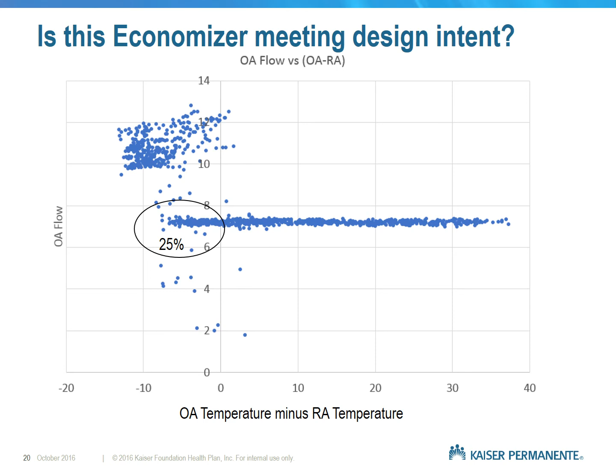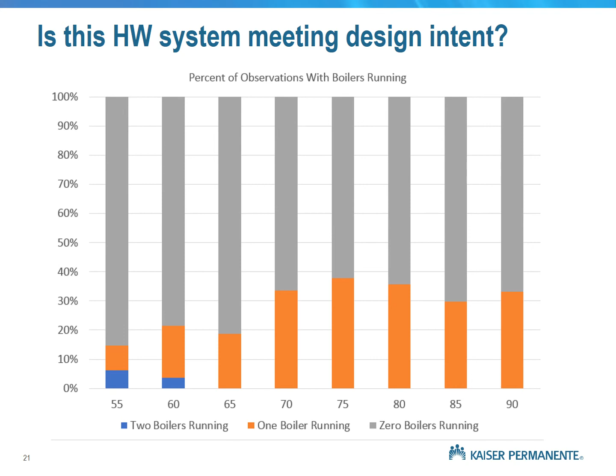What about this? This really simple idea of putting outside air on the x-axis can really change the way we look at trend logs. So, if you take a look at this picture, would you say that this boiler system is running according to its design intent? This is 15-minute interval data, and gray means there's 0 boilers running, orange means there's 1 boiler running, and blue means there's 2 boilers running. So as outside air temperature increases, we should see fewer boilers running, or boilers running less often, right? We're not seeing that.